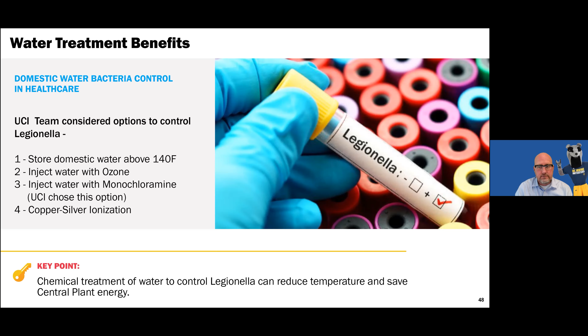And for years, the 140 degree Fahrenheit storage temperature has been the default method, but that would result in a very inefficient heat recovery chiller operation requiring excessive electrical power input. So we went with the monochloramine, but the main point here is that chemical treatment of Legionella is actually a low energy option as opposed to the energy it takes to store water above 140 degrees. Go ahead, Tom.